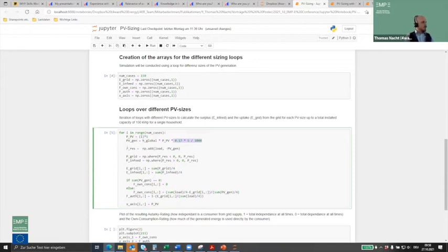And then we calculate the residual load, so how much surplus or how much grid uptake there is per quarter hour. Then we calculate the power taken from the grid and the power fed into the grid per quarter hour, and sum that up to get the energy. And then we calculate the own consumption factor and the autarky rating for this building. So as I mentioned, this is nothing too fancy in terms of modeling, but it is a good approach.